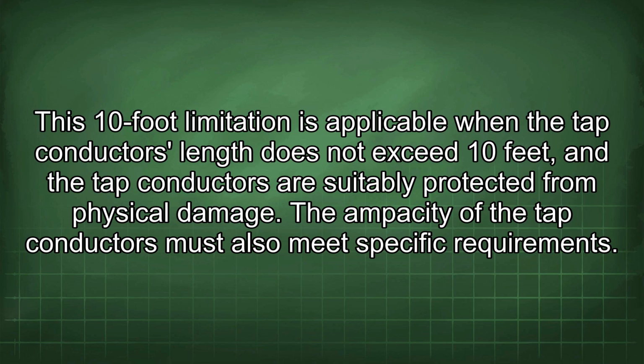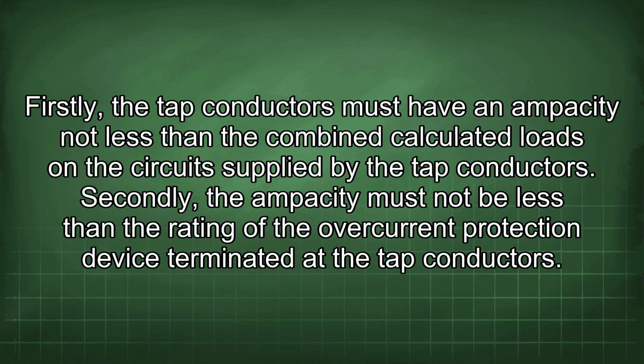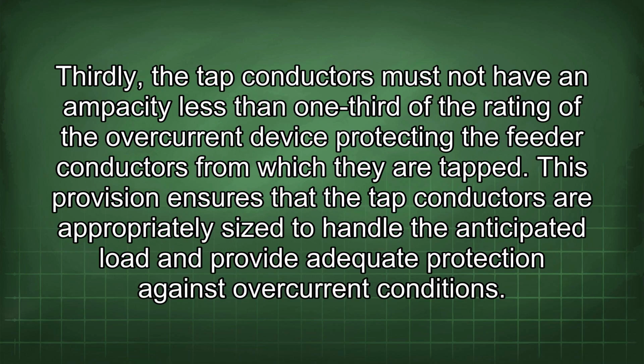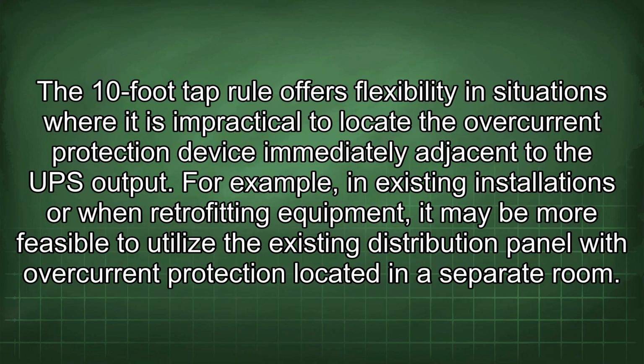The ampacity of the tap conductors must also meet specific requirements. Firstly, the tap conductors must have an ampacity not less than the combined calculated loads on the circuit supplied by the tap conductors. Secondly, the ampacity must not be less than the rating of the overcurrent protection device terminated at the tap conductors. Thirdly, the tap conductors must not have an ampacity less than 1/3 of the rating of the overcurrent device protecting the feeder conductors from which they are tapped. This provision ensures that the tap conductors are appropriately sized to handle the anticipated load and provide adequate protection against overcurrent conditions. The 10-foot tap rule offers flexibility in situations where it is impractical to locate the overcurrent protection device immediately adjacent to the UPS output.